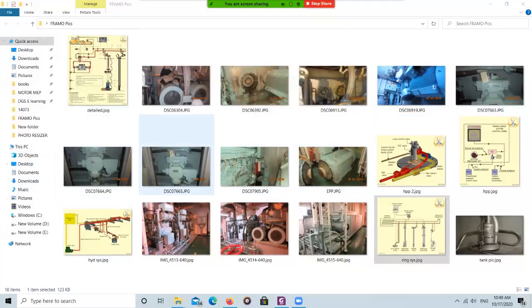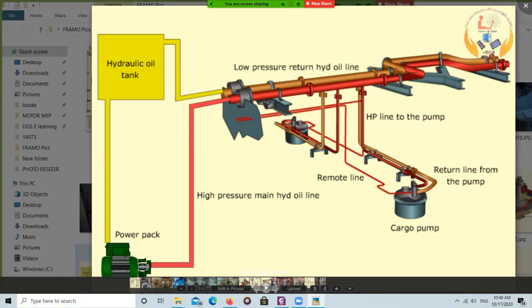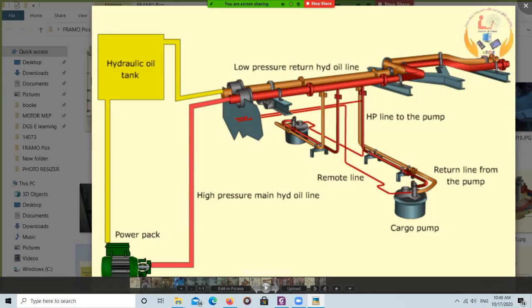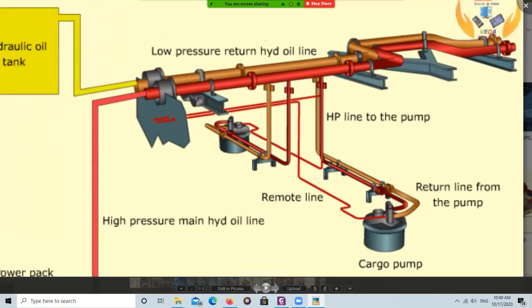Behind this bulkhead is the engine room, so the hydraulic oil tank and power packs are located inside the engine room, while all the hydraulic system pipework is on deck. On the tank dome, you have the speed torque controller connections. The red line is the high pressure hydraulic line on deck — this is the main high pressure line — and branches are taken to drive each pump. This is the hydraulic oil return line.